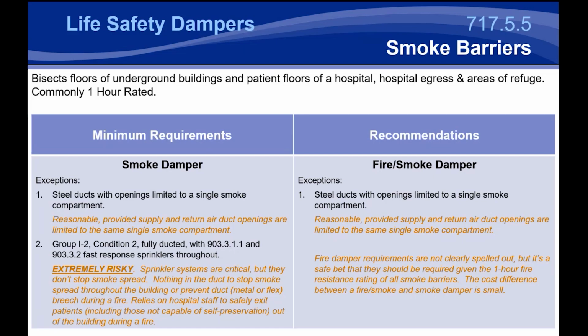So these 1 hour rated barriers and corridor walls or carriage suites still needed a fire damper to protect them. Now, with that fire damper, you would often have to have some type of control to tie into a smoke control system, or you have a fire damper with a fusible link where you don't know if it's going to be open or closed, and that will interfere with the smoke control system. So rather than removing that fire damper requirement and potentially leaving a rated barrier unprotected, we typically recommend putting in a fire smoke damper, as they will both be tied in. There's a fire rating for that and a smoke rating.